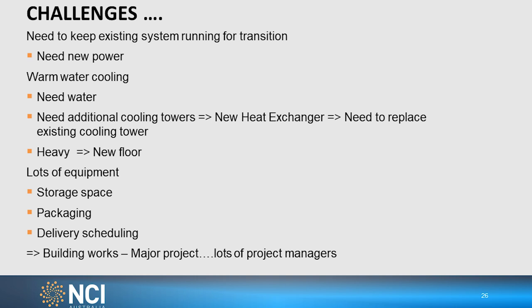Warm water cooling implies that you need some water, and in this part of the data center, there was no water. So we need additional pipe work, additional cooling towers, new heat exchangers. And because of the limited space, we actually have to replace one of our cooling towers with a larger cooling tower.